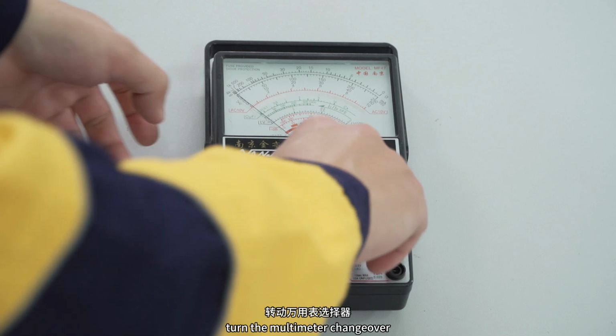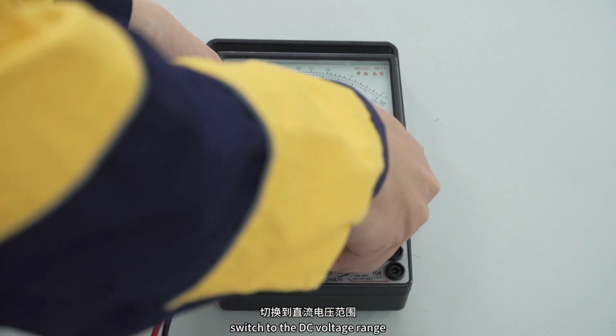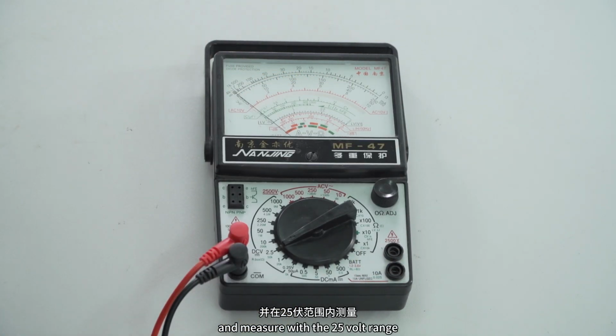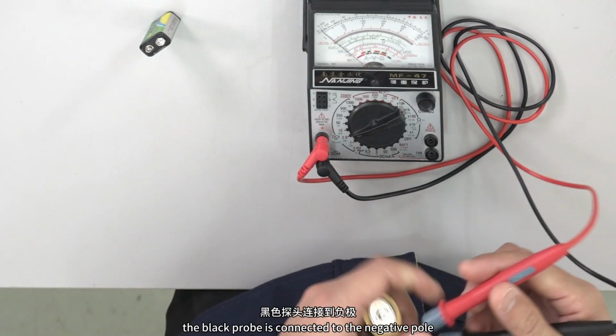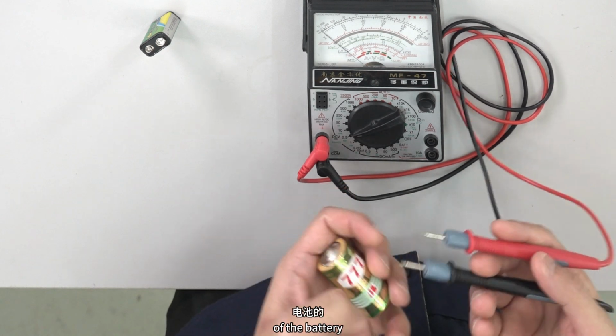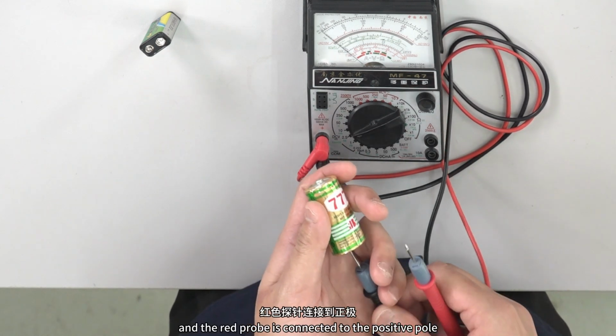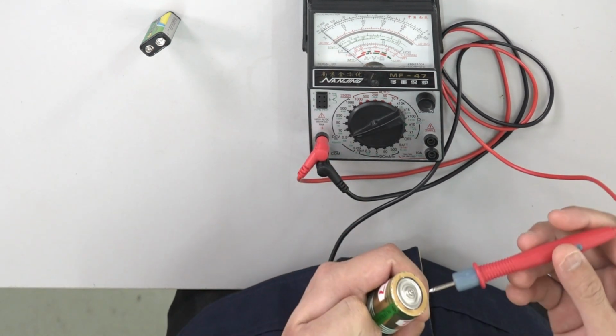Turn the multimeter changeover switch to the DC voltage range, and measure with the 25-volt range. When measuring voltage, try to make the measured reading close to the selected range, but not greater than the range. This makes the reading more accurate. The black probe is connected to the negative pole of the battery, and the red probe is connected to the positive pole.